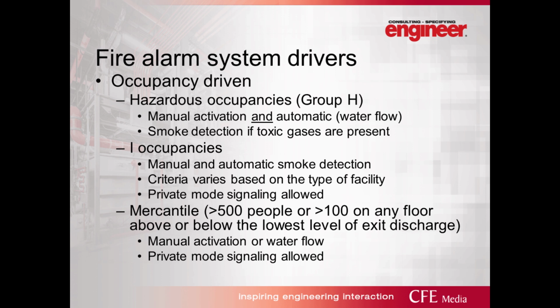Mercantile occupancies, you can see a pretty high threshold for when a fire alarm system is required, greater than 500 people or greater than 100 on any floor above or below the lowest level of exit discharge. And this is one of those occupancies, again, where you're not required to have the manual pull boxes if you have water flow indication.